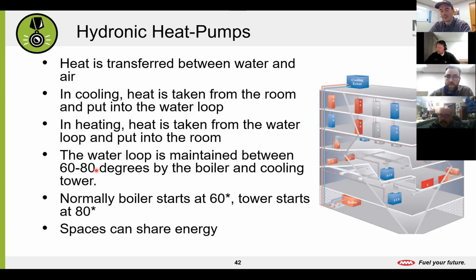Typical set points, and this will really vary depending on what building you're in, but a water loop is usually maintained between 60 and 80 degrees. You'll often hear us call that the condenser water loop. Normally your boiler would be set at 60 degrees. So if it gets colder than 60 degrees, the boiler would turn on down in the basement and heat up the water. So the minimum temperature of the water being supplied to these units is 60 degrees. In the summer, when we're running AC and we're pulling a lot of heat from the air and putting it into the condenser water loop and heating it up, we have a cooling tower that makes sure our condenser water loop doesn't get above 80. So if it does, it'll turn on and reject that heat there. And then, just like with VRF, that variable refrigerant flow, we have variable water flow. Let's just call it that. So spaces can share energy.